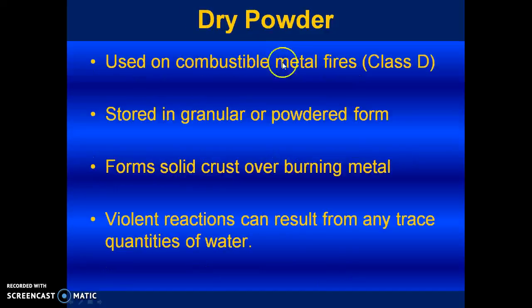Your dry powder, used on combustible metal fires. It's stored as a granulated or powder form. Forms solid crust over the burning metal. These are the ones you need to be careful of as a Class D with the violent reactions from water. If you put water on these, it will blow up in your face or have a severe reaction.